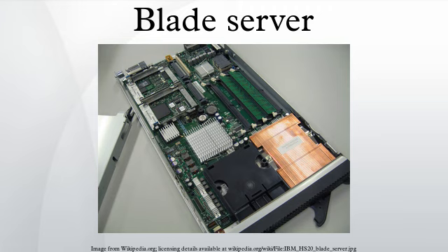In absolute terms, a fully populated rack of blade servers is likely to require more cooling capacity than a fully populated rack of standard 1U servers. This is because one can fit up to 128 blade servers in the same rack that will only hold 42 1U rack mount servers. Networking.